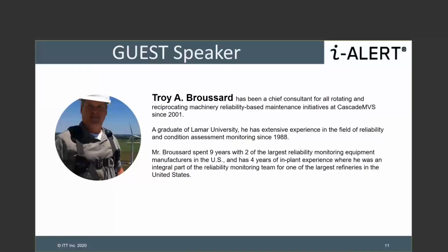So we did, and what we found was it needed to be balanced again. So we balanced it. It was a 2-hour start to finish, and they were back up and running within 2 hours. I asked the CFO if he could share some data with us. So a $1,000 investment in iAlerts showed about a $17,000 cost savings, because normally they would have run this to failure if they didn't have a way of monitoring it.